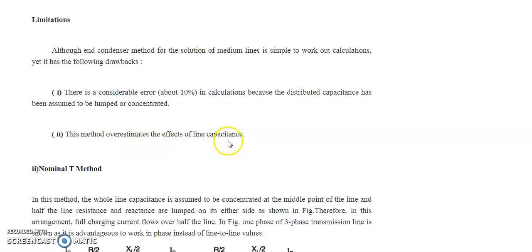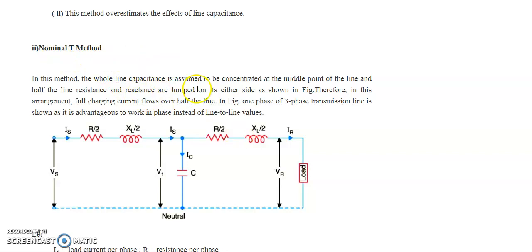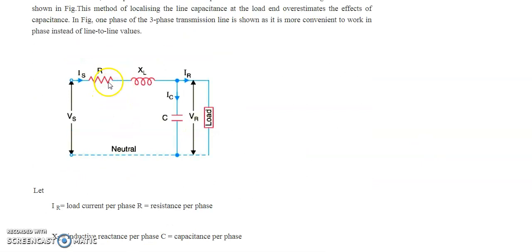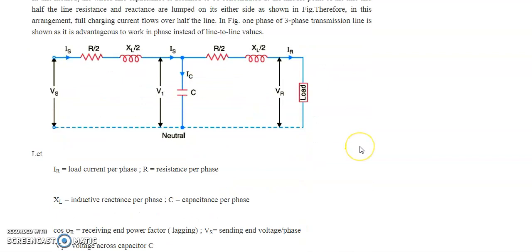The next method is the nominal T method. Here, the total capacitance of the line as a lumped element is considered at the midpoint of the transmission line. For example, for a 100 km line, the capacitance is placed at 50 km. Half the total resistance and half the reactance are lumped on the sending end side, and the other half on the receiving end side. This gives the T-shaped equivalent circuit.